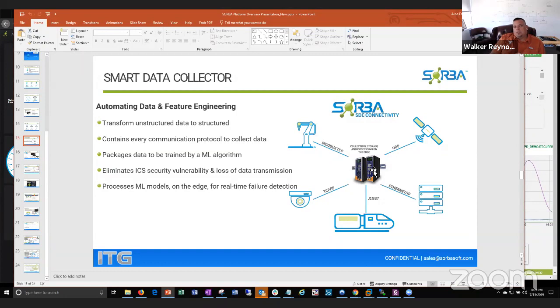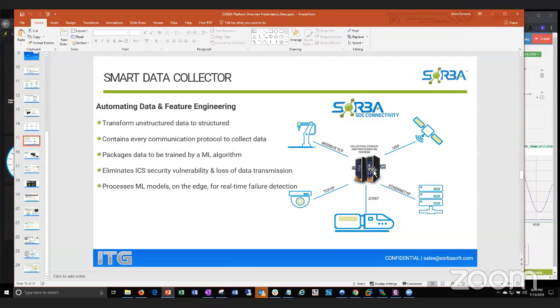So does that edge device talk MQTT, OPC UA? Can it be an OPC UA client against another system? Absolutely, yeah. In fact, OPC UA has typically been how we connect, mainly because customers already have either Kepware or some type of OPC server. The reason I bring up the built-in drivers is that if you have a standalone compressor, generator, or equipment not built into your infrastructure, the ability to connect the device directly through some industrial protocol is really the advantage.